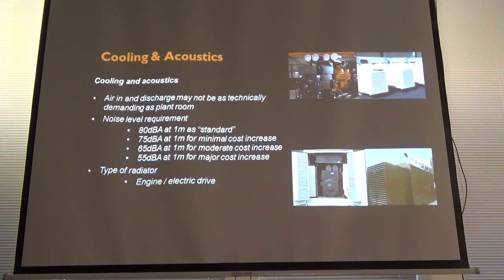Overheating, it's not ideal. But what's changing is we're monitoring it. We've got telematic systems now which will actually monitor that unit. So we'll give them feedback and say, look, this is what your set's running. Are you planning to increase the load on this? Oh, no, not really. So you can halve the size of the unit. We've just saved you an awful lot of cost, and you can monitor it more. So technology is moving forward with that.